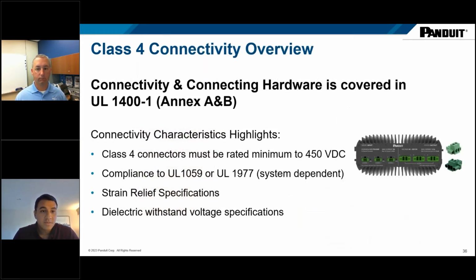I won't talk a lot about the connectivity, but again, UL 1400-1 Annexes A and B do cover requirements on the connectivity. And one main thing to highlight here is that the connectors you end up using with your system must be rated for that minimum of 450 volts.